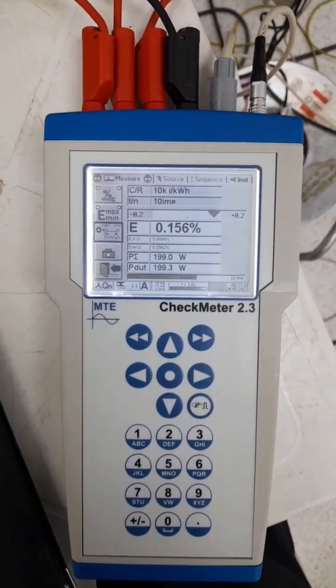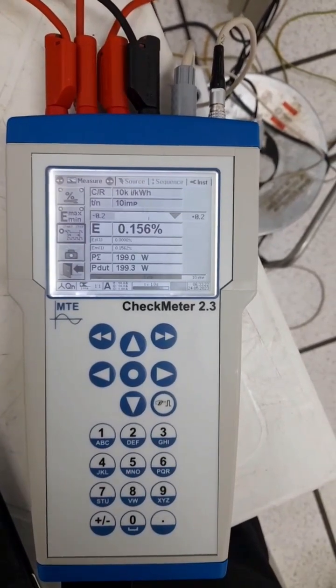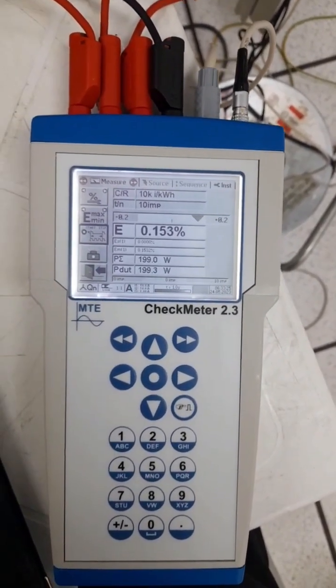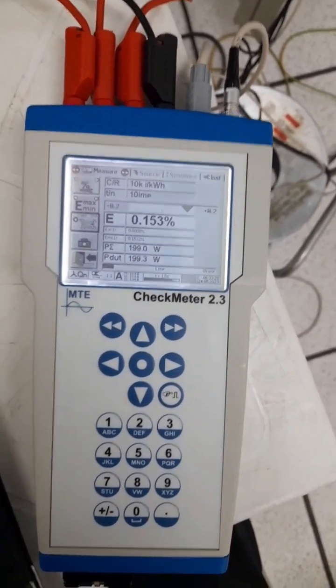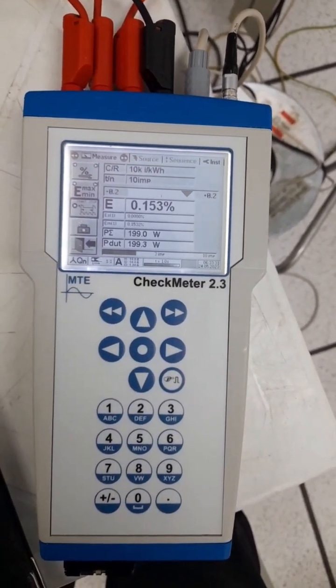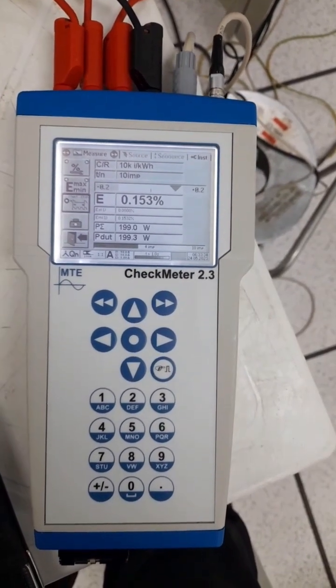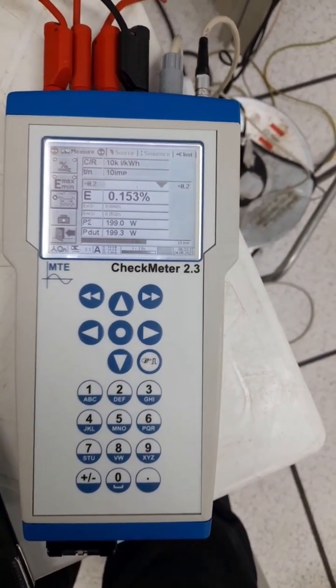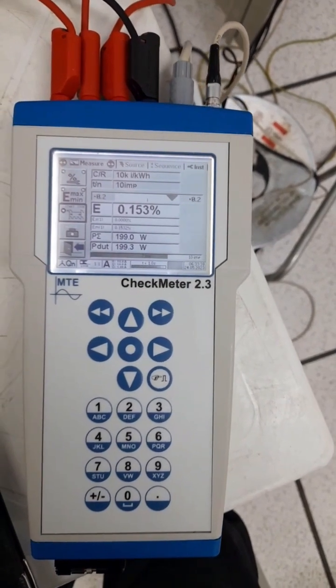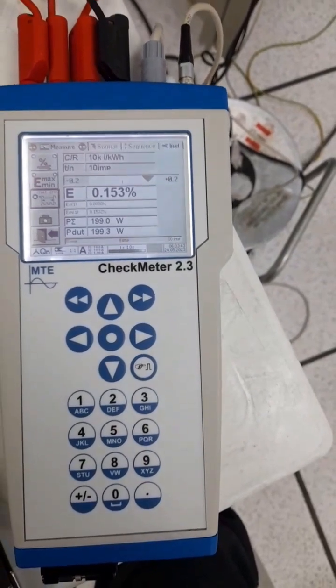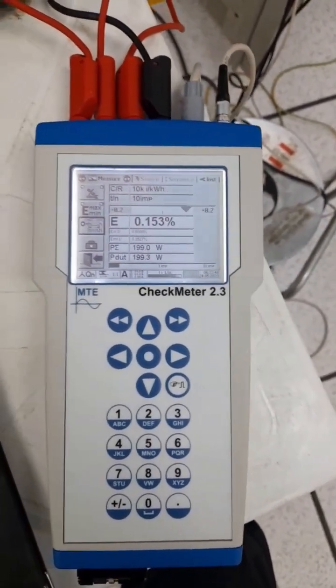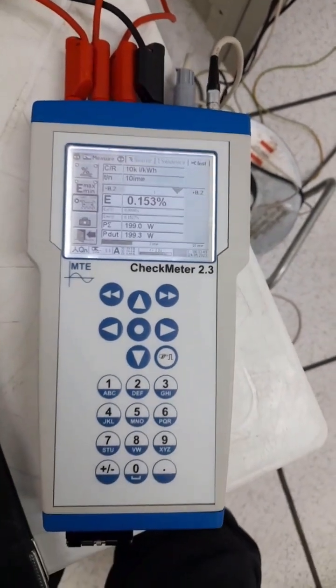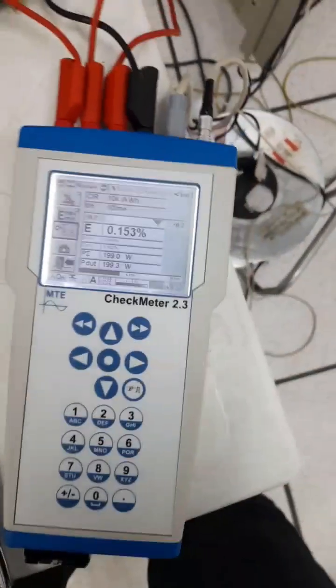Okay, now the error calculated value is under the limit. Before I recorded the video, the error was more than 0.2. The reason is the current clamp. One reason should be your current clamp must be fixed properly. Another reason will be your scanning head installation. This scanning head installation can be ensured based on that LED pulse, and this current clamp will make a huge impact.